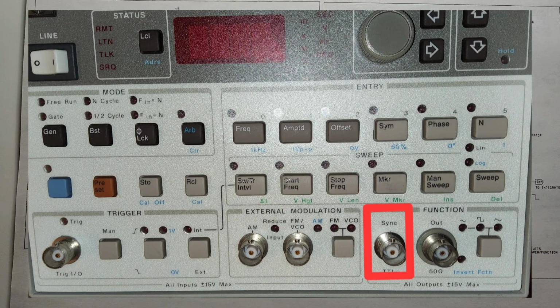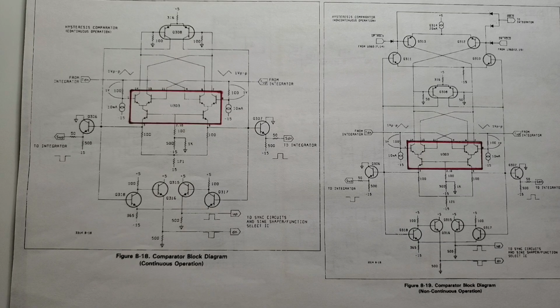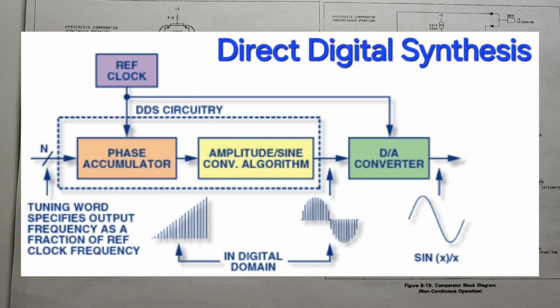And that's because we always need to generate a consistent synchronized signal to be used as a sync output for external use and as a feedback for frequency calibration. So that's sort of a broad brush, high-level overview of how it's supposed to work. Longer than a few minutes describing an old equipment, but I thought you might find it also interesting, in comparison to modern units that use direct digital synthesis with fast memories and fast CPUs and so forth. So with that, we'll move on to start testing the unit.